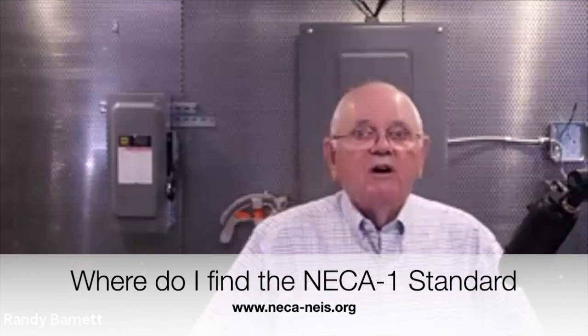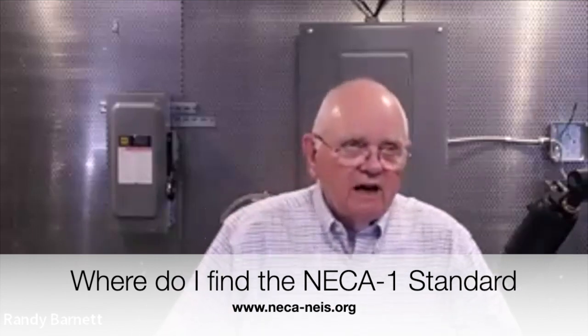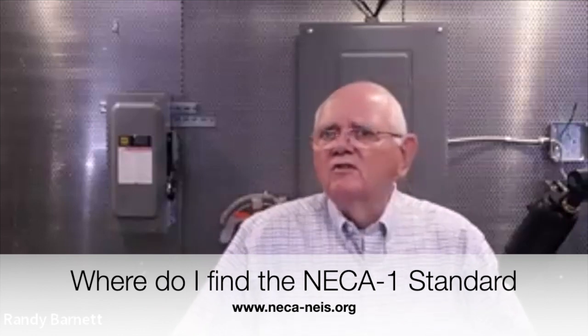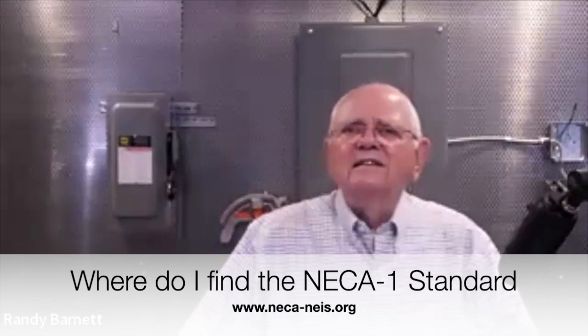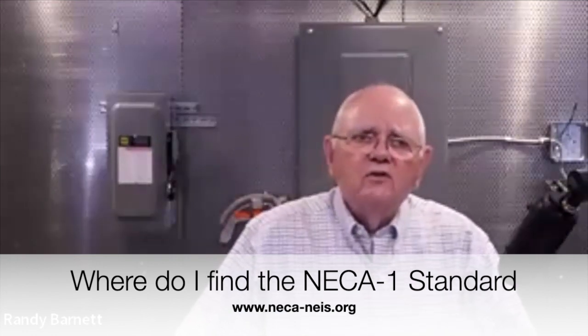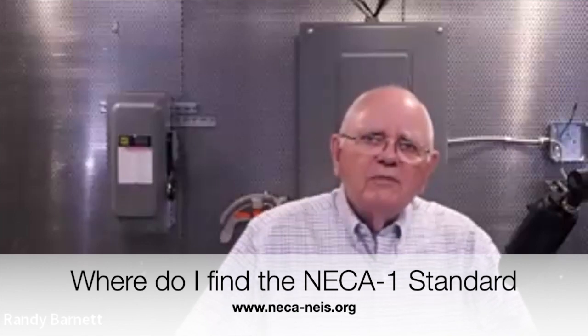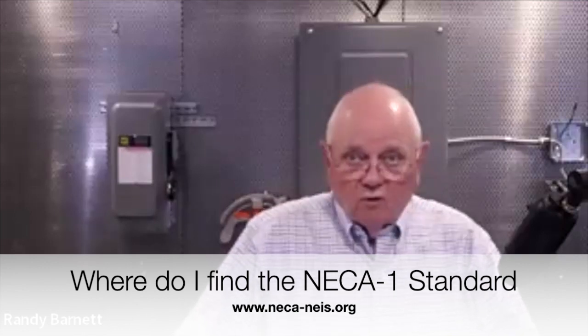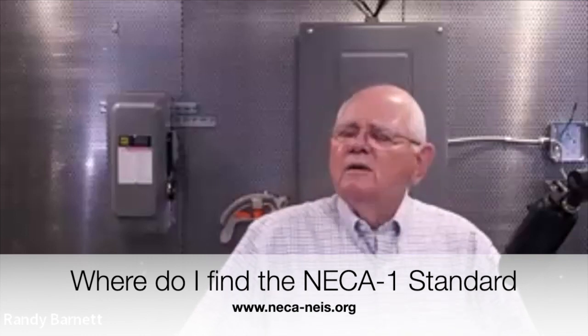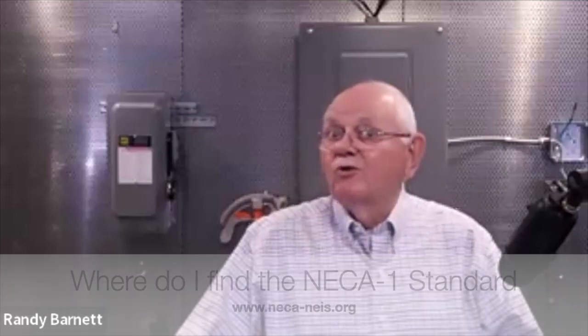If we're short of any parts, if they're back ordered, which might be common, we need to note on the inventory what parts are back ordered. Then we need to close it back up. We don't want to unpack it entirely, just enough so that we can inventory it and inspect it, close it back up and keep it free of dust, dirt, moisture, any type of contamination. Keep in mind, I certainly don't want to store that in a corrosive area where it's going to be subject to corrosion and so forth. So that's what chapter 2 of the NECA 1 standard is talking about.